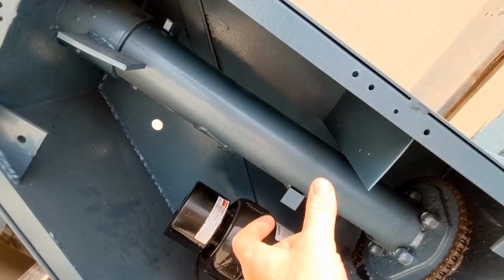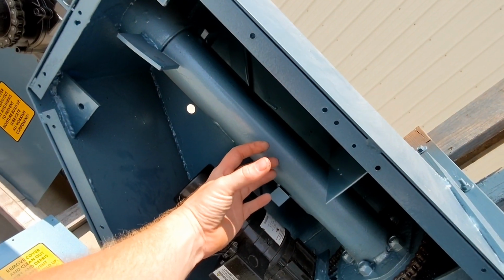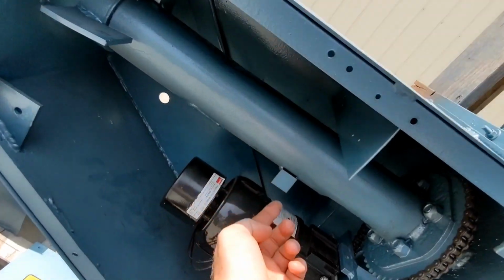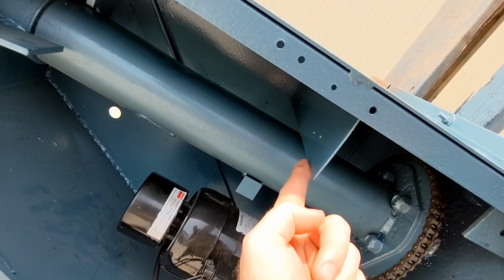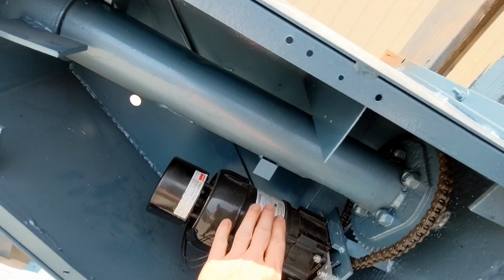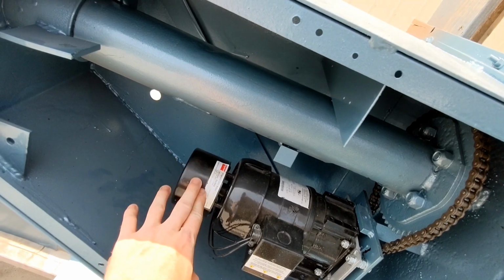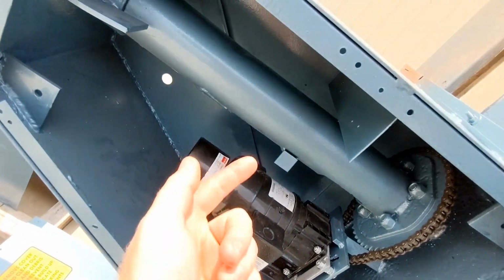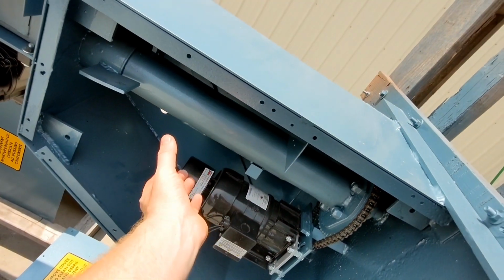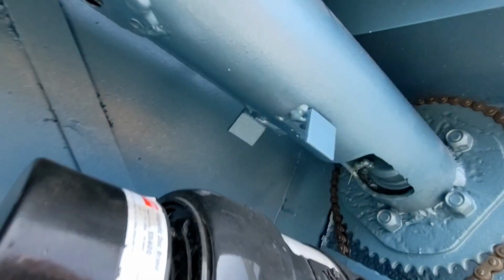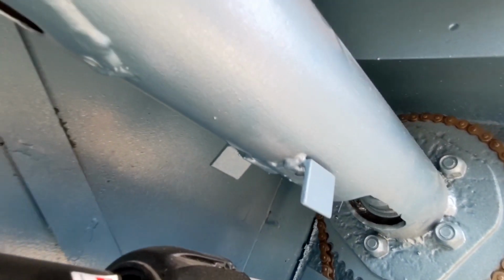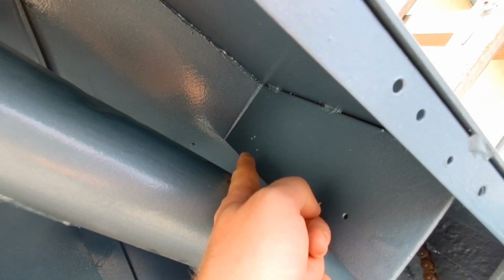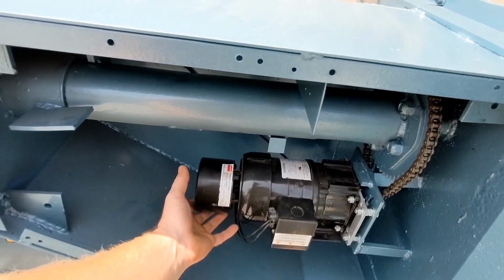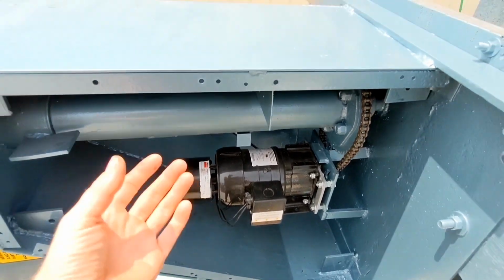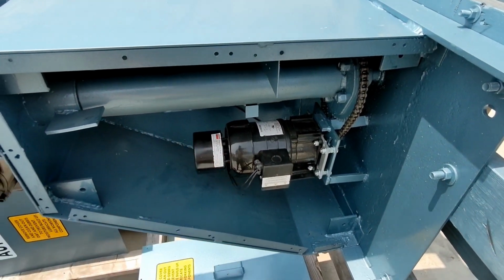These tabs welded onto the column rotate with the column, and when it reaches its maximum turning to the left, this would contact the spring-loaded arm on the micro switch, cutting power to the motor, and the brake would stop the motor instantly. Then if the switch is reversed and the probe spins to the right, the opposite tab would hit the spring-loaded arm on the micro switch, cutting the power, and again the brake on the back of the gear motor would stop the swivel action instantly.